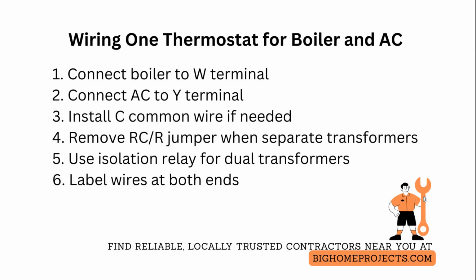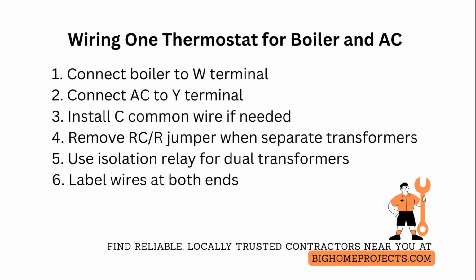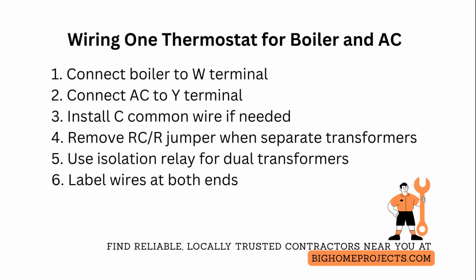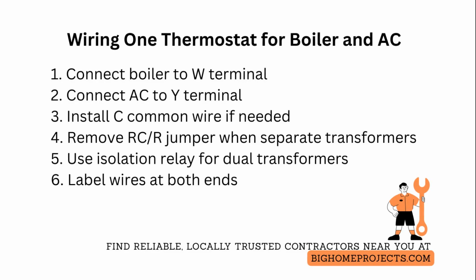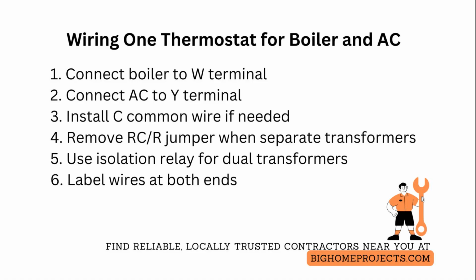For older boilers that use millivolt or hydronic controls rather than 24 volt thermostats, use an isolation relay or a zone control interface that lets the thermostat operate the boiler safely without passing line voltage back to the air conditioner controls. Finally, if you are unsure about transformer ownership, inspect the equipment circuit boards. A 2-transformer setup will have 2 separate 24 volt outputs clearly labeled, and the correct fix is to isolate the thermostat electronics from one of those outputs using relays or a control board kit.